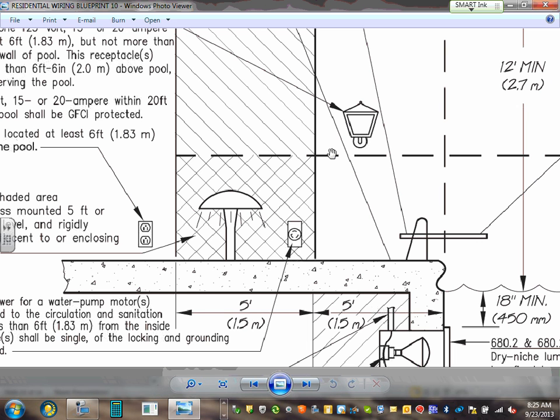To be not less than 7.5 if GFCI protected. If less than 7.5, it must be GFCI. You actually can go lower for the spa. You can go lower than 7.5, but it has to be listed for that location and still GFCI. Measured from the highest top of the water. What about the equipment that's running the pool? That's GFCI also? Yes, if they are 15, 20, 30 amp, 120 or 240 volt. If they're 3-phase, it's different, but in our project they're all single phase, so they have to be GFCI.